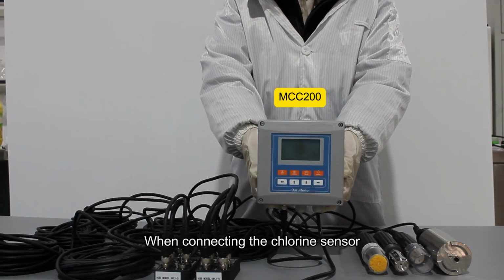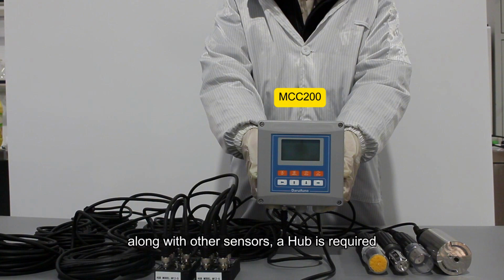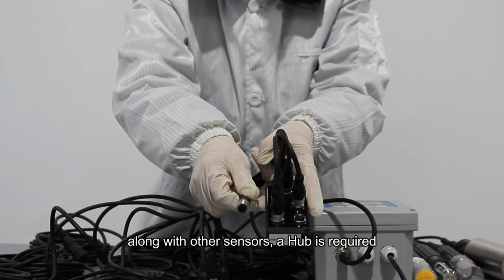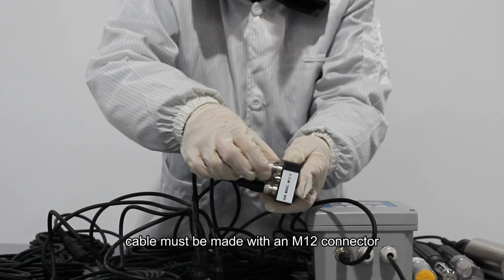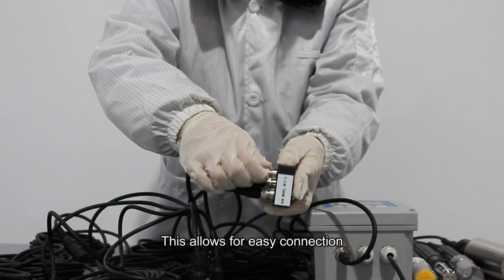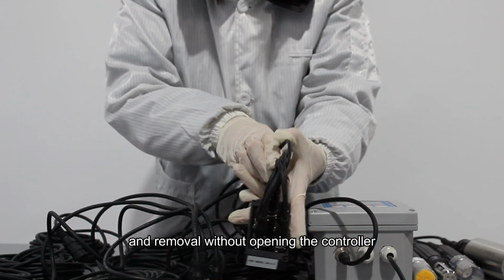When connecting the chlorine sensor to an MCC series multi-parameter controller, along with other sensors, a hub is required. The other end of the gateway cable must be made with an M12 connector to connect to the hub. This allows for easy connection and removal without opening the controller.